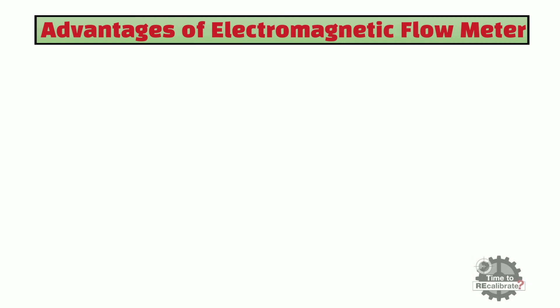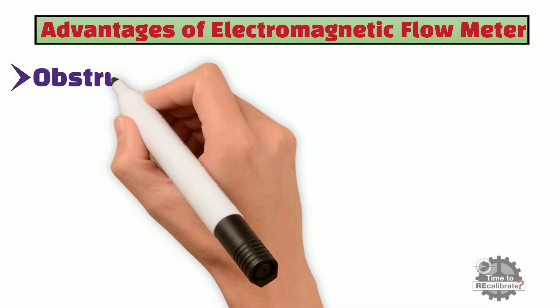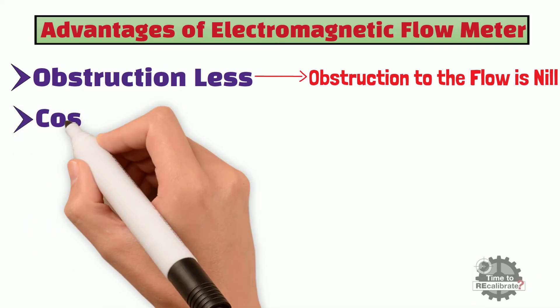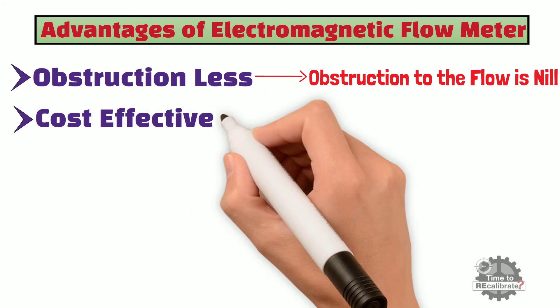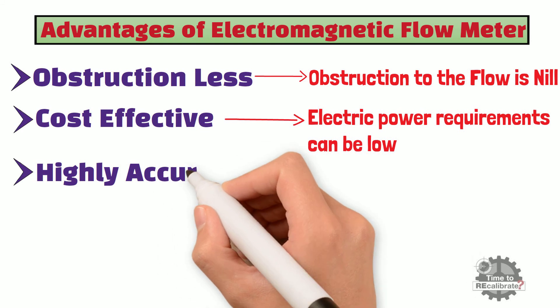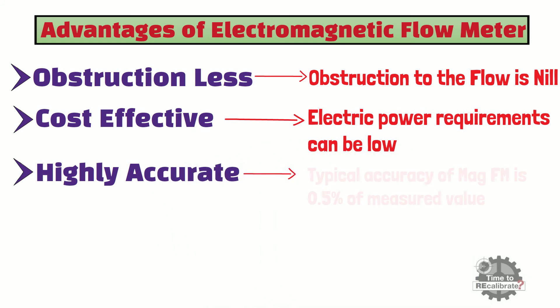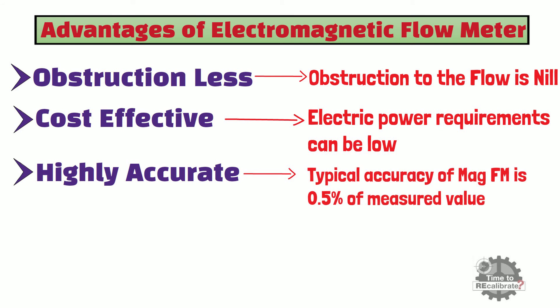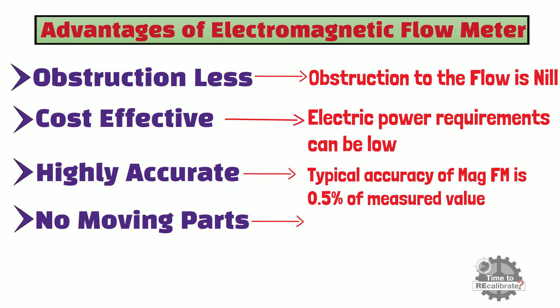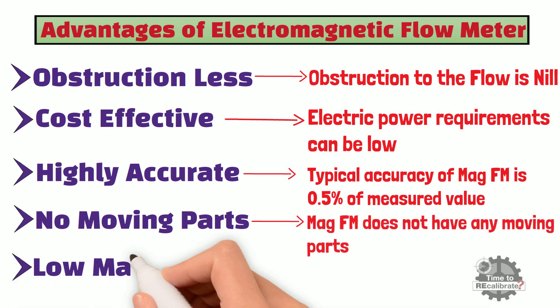The advantages of electromagnetic flowmeters are: first, they are obstructionless — obstruction to flow is almost nil, making them suitable for heavy suspensions including mud, sewage, and wood pulp. Second, they are cost-effective, with low electric power requirements, particularly with pulse DC types. Third, they are highly accurate, with a typical accuracy of 0.5% of measured value. Fourth, they have no moving parts. And finally, they are almost completely maintenance-free.